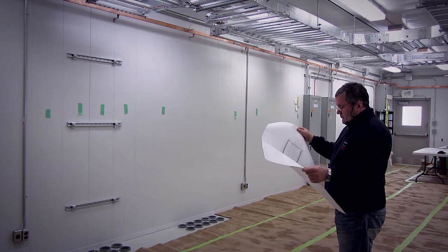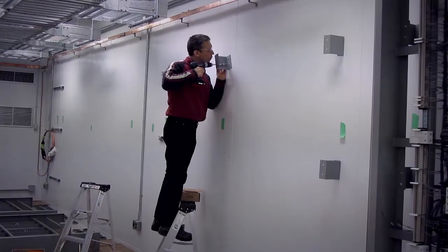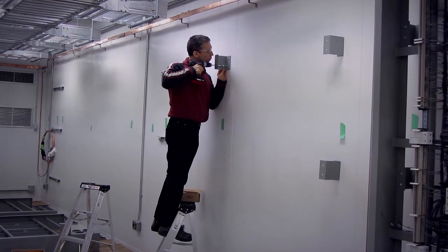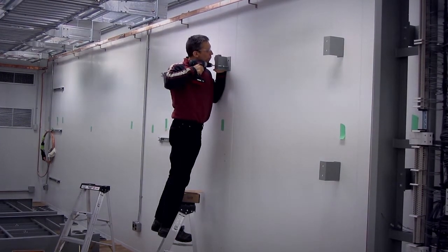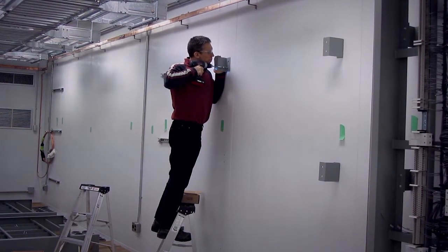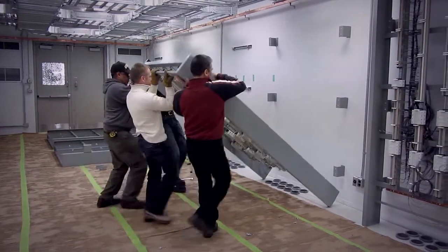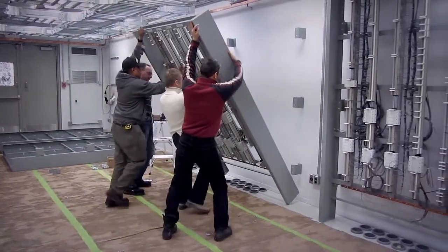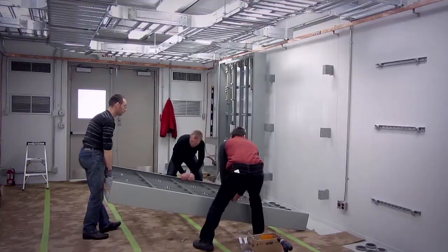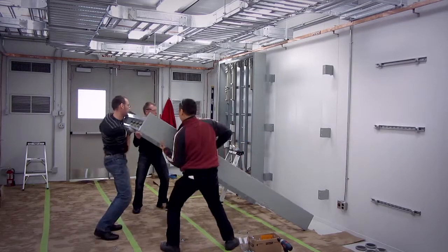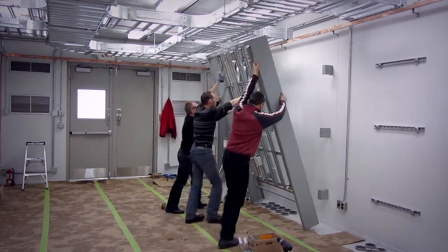Once again, layout drawings are issued for construction. Main components and assemblies for AC and DC power supply are mounted on the walls. The termination racks, where all the final external substation cables will be landed, are installed in the building and secured in place. Once the major wall-mounted components are in place, the floor-standing panels can be installed and braced.